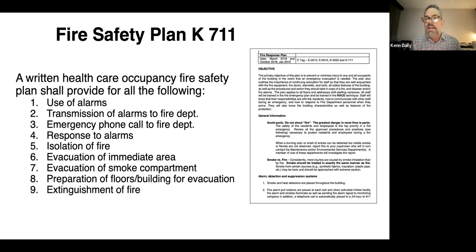How your alarm is initiated, that's the transmission, that's through the pull stations, also through smoke detection devices, and maybe even heat detection devices that are connected. You have the emergency phone call to the fire department, which is required. I'm sorry, the incident commander would call your fire 911 service. Obviously, a monitored fire alarm also will send a signal to a monitoring company, which then has 90 seconds to also call 911 or your emergency. It's all about overlap and redundancies.